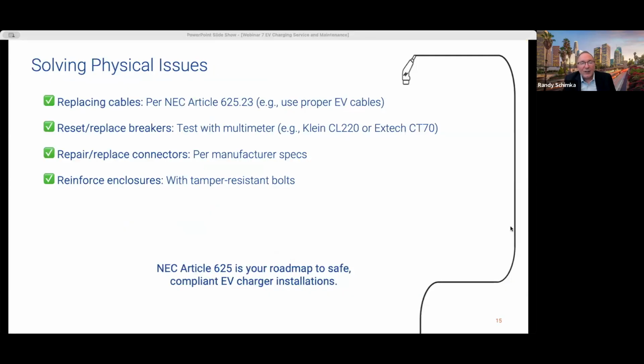Let's tackle solving physical issues to keep EV chargers running smoothly, guided by the steps here. First, when replacing cables, follow NEC Article 625.23, which mandates using proper EV rated cables to fix cuts or insulation faults. This ensures safety and compliance while restoring reliable charging. Next, when it comes to resetting or replacing breakers, you can use a multimeter like the Klein CL220 or the Extech CT70 to test for frequent tripping or degradation. Resetting or swapping out faulty breakers can help to prevent power disruptions.